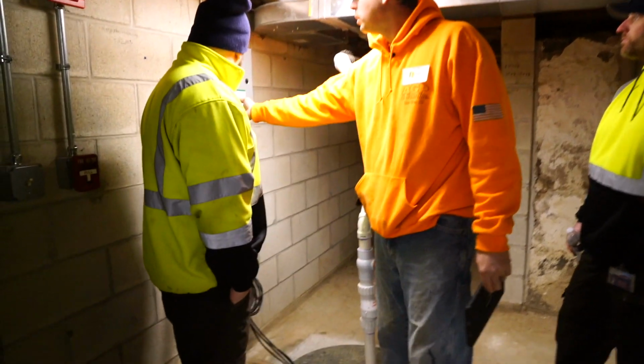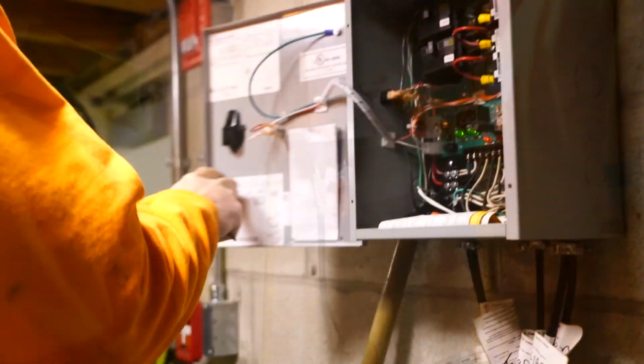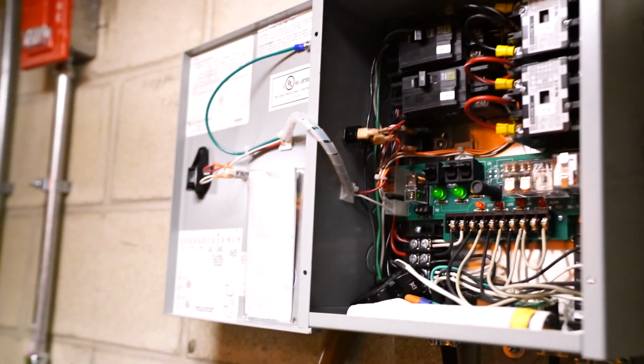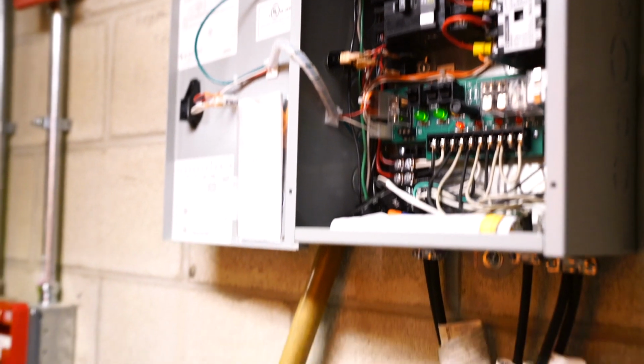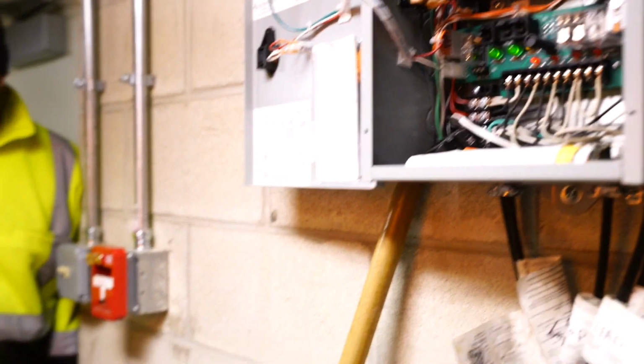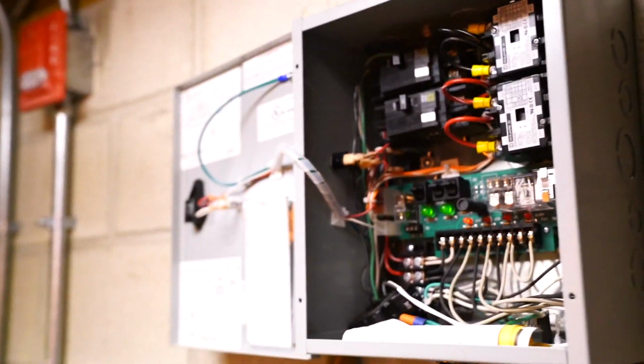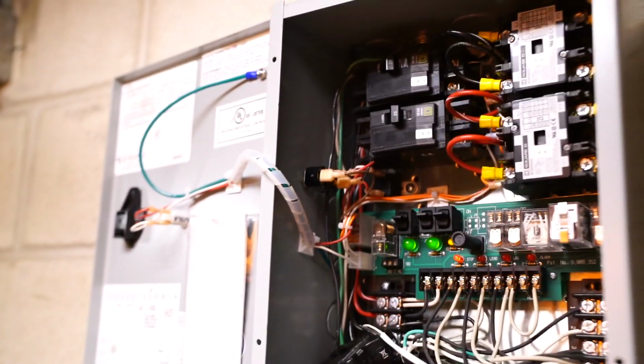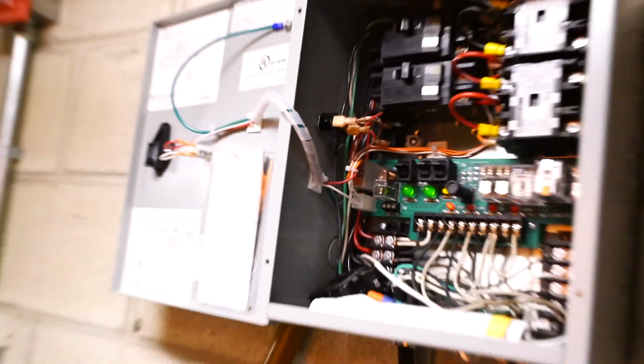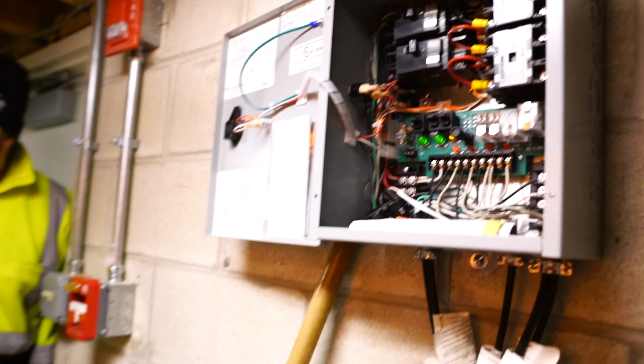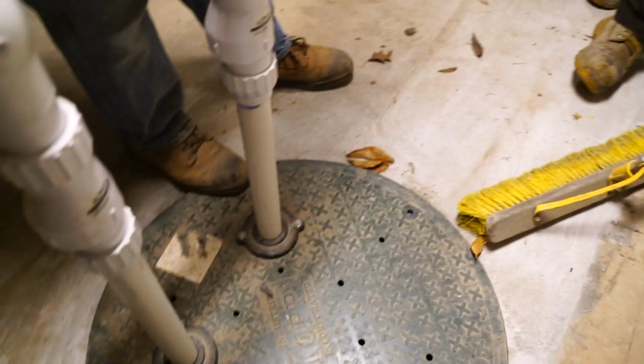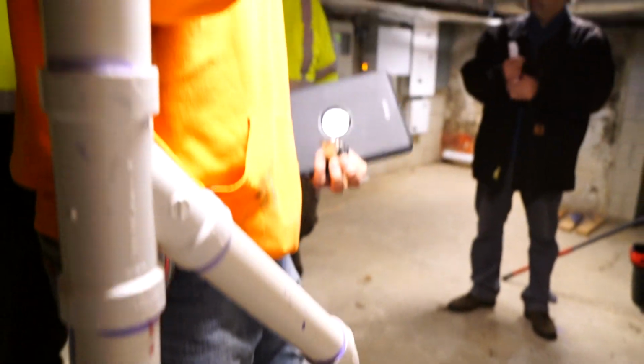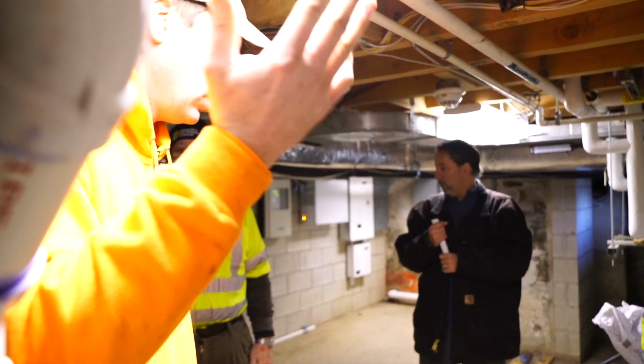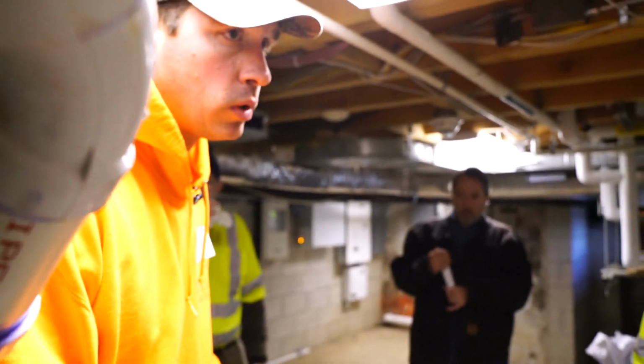This will have an alarm. You have three floats in here. It's basically an on, an off, and an alarm. Water gets to a certain height, kicks it on. Water goes back down to a certain height, that float goes down, turns it off. If it ever gets above to the third float, that's the highest in the tank, the alarm will go on.